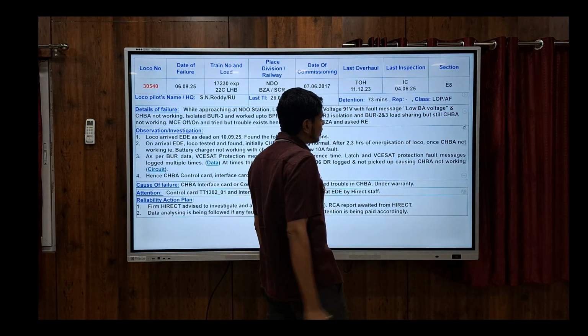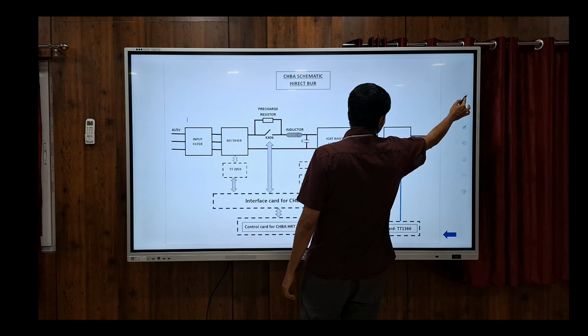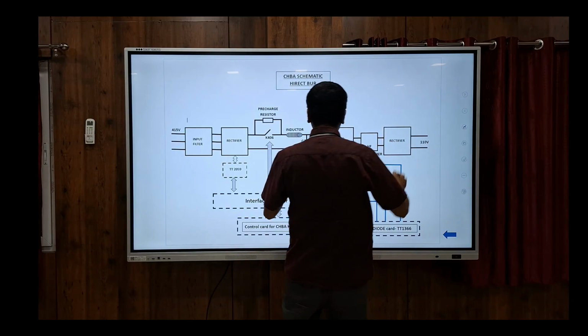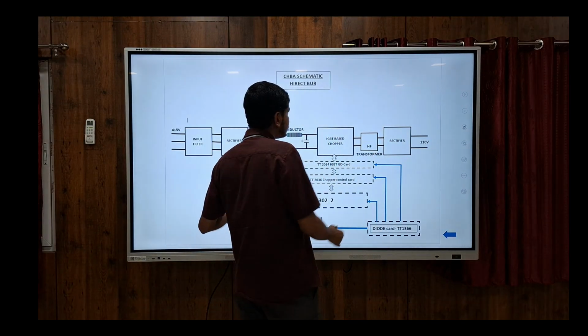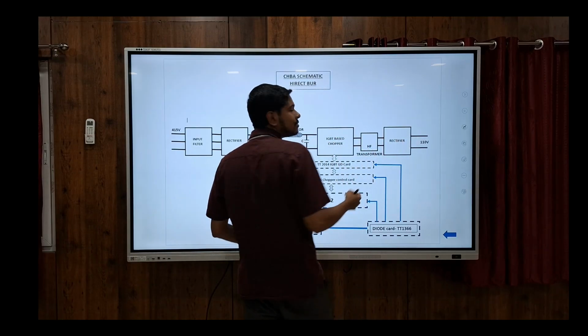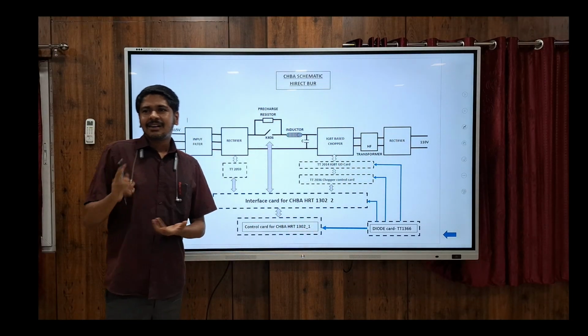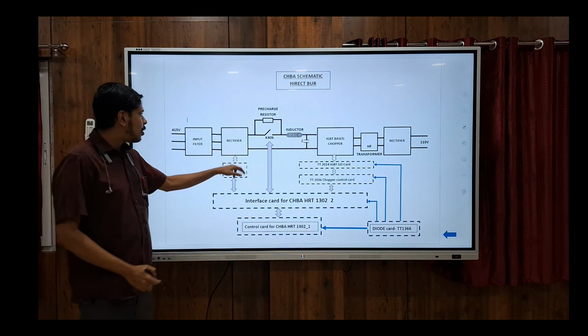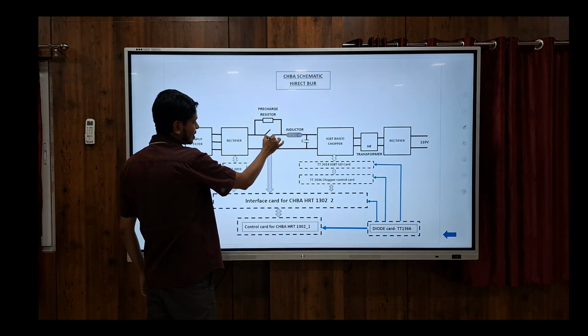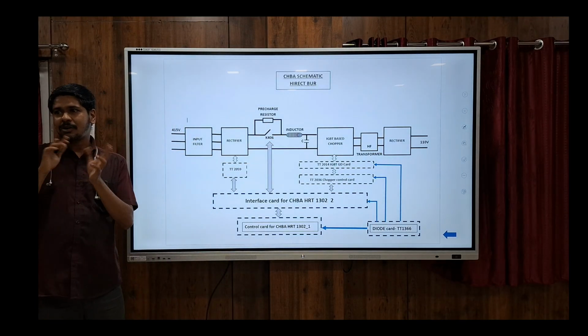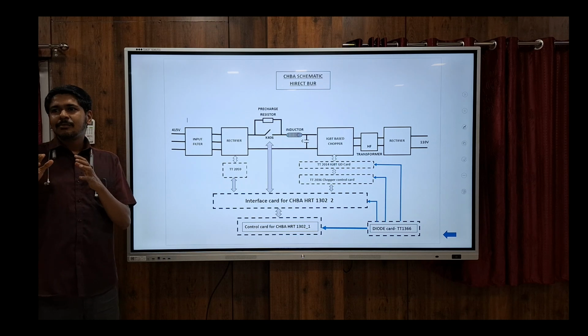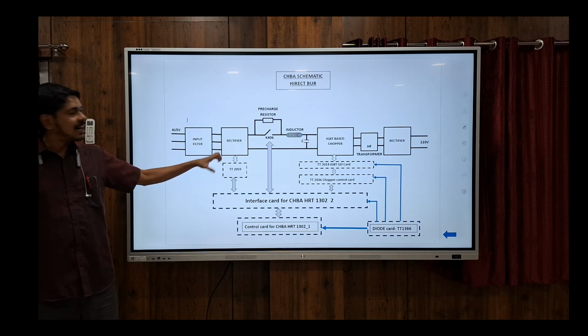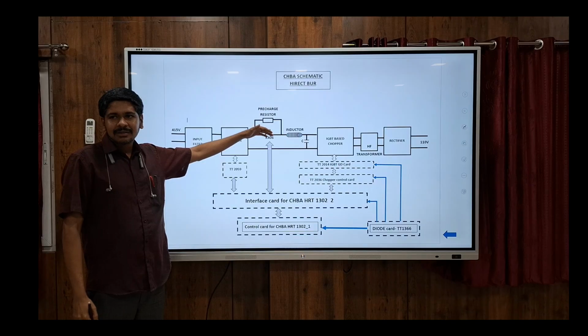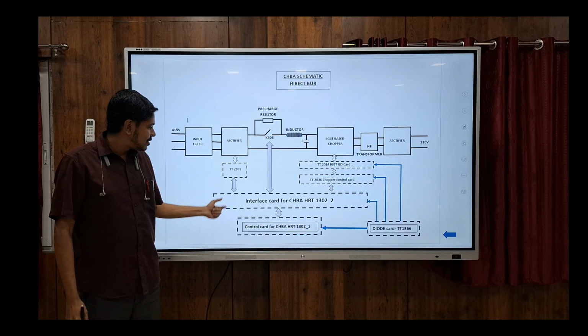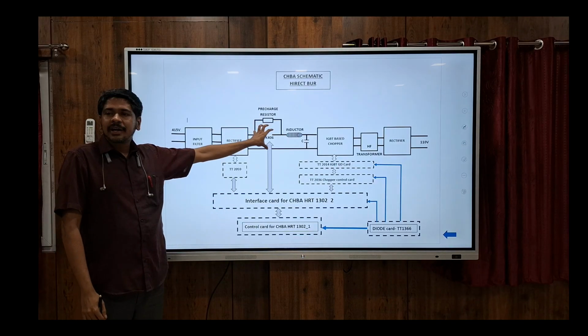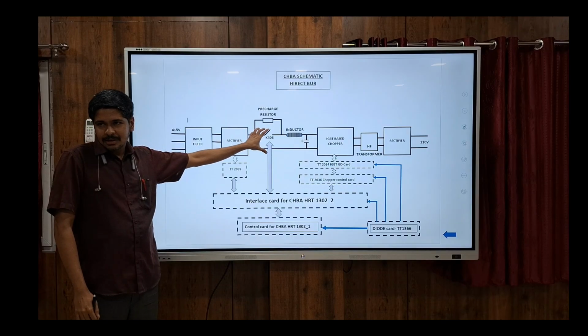Then 30540, this is a HIRECT make battery charger. I have previously explained the circuit. In that, multiple problems are there. In February we got this contactor stuck in off, stuck on condition alternatively, because it was not a permanent failure - at times this contactor would not work. That resulted in the failure. At that time actually the contactor was in good, healthy condition only.